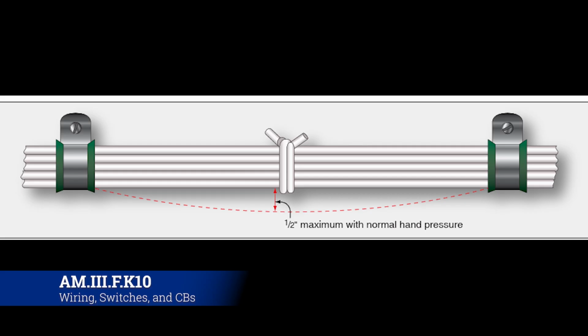If you put it in there super tight, what you effectively do is induce stress and strain into the wire that will cut into anything it can. So if that Adel clamp wears through the rubber grommet, and it falls through, or gets cut, or dry rots, it attaches to the metal. If it's slack, it will sit there, and you have a lot more time to catch that fault before it actually starts to cut into the wire. If it's super, super tight, it's going to bear down on that metal edge, and it'll cut through it a lot faster.